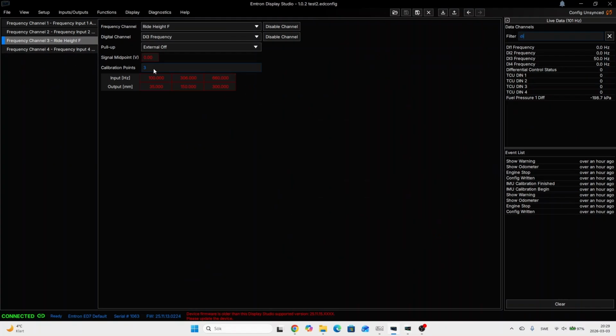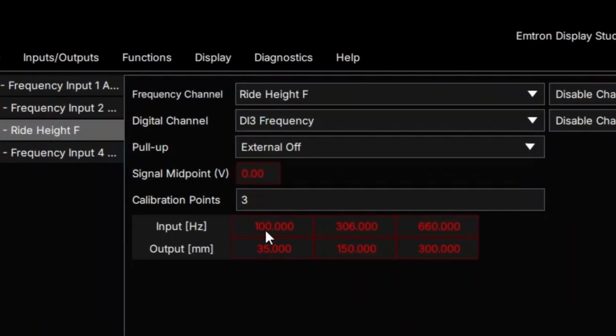And then I went ahead and made a 3-point calibration table, and it shows 100 Hertz, 306, and 660. The numbers are a bit random, but it was the easiest way, because I had some issues adding decimals here for some reason. So 100 Hertz at 35 millimeters, 306 Hertz at 150, and 660 Hertz at 300 millimeters, and that worked.